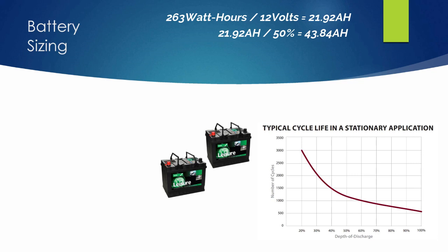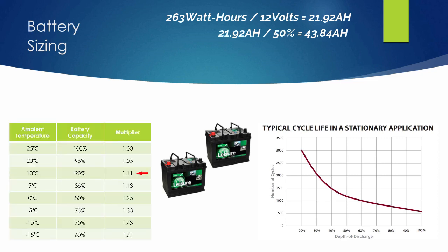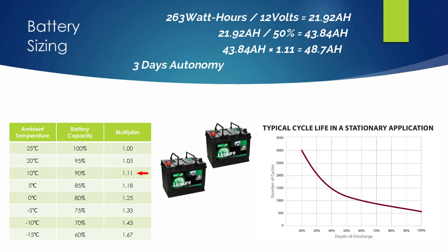One more thing to consider is the ambient temperature the battery will be stored in, as it does affect battery output. From the table, at 10 degrees Celsius the multiplying factor is 1.11. So we take our 43.84 amp hours multiplied by 1.11 to get 48.7 amp hours for one day. If we didn't have sunshine for a couple of days due to cloudy weather, we'd want a couple of days of autonomy. Multiplying 48.7 amp hours by 3 days gives a total of 146.1 amp hours — so a 150 amp hour battery will be plenty for this single 120 watt panel.